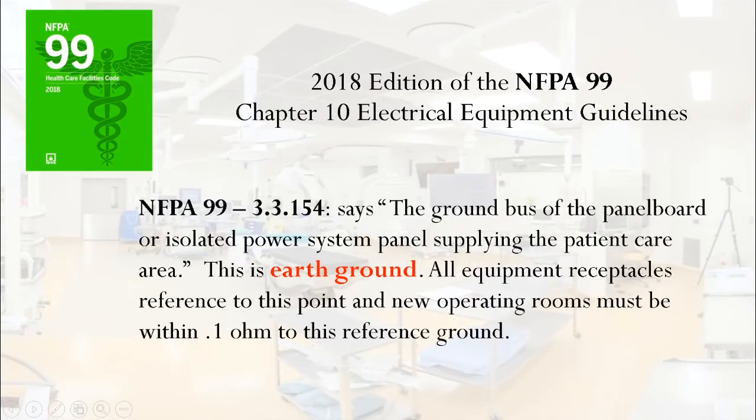NFPA 99 3.3.154 says the ground bus of the panel board or isolated power system panel supplying the patient care area — this is earth ground. All equipment receptacles referenced to this point, and new operating rooms must be within 0.1 ohm to this reference ground. This means the panel board that has the isolation transformer in it is grounded to earth ground.